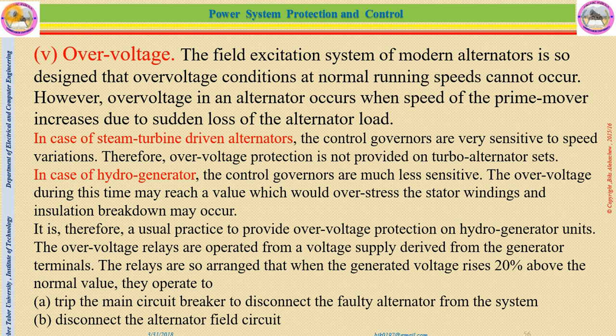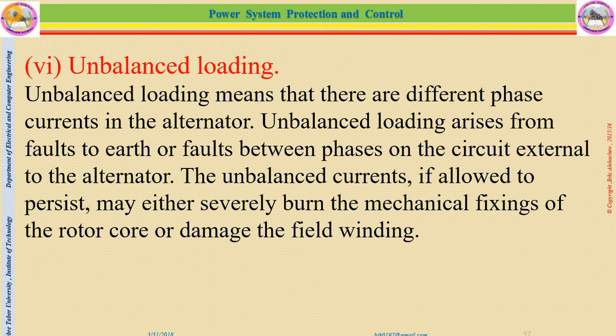For example, in case of a steam turbine driven alternator, the control governors are very sensitive to speed variations. Therefore, overvoltage protection is not provided on turbo alternators. In case of hydro generators, there may be some damages. The overvoltage may damage some insulations. So it is usual practice to provide overvoltage protection on hydro generators.